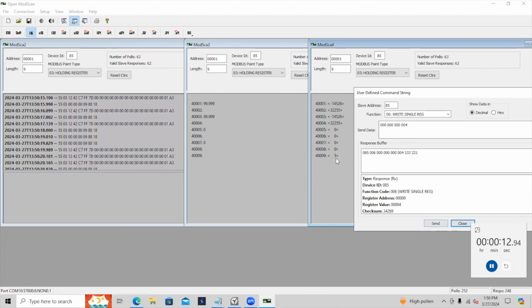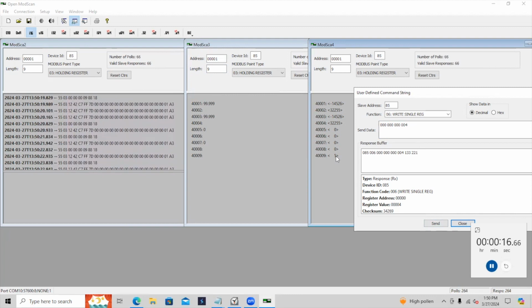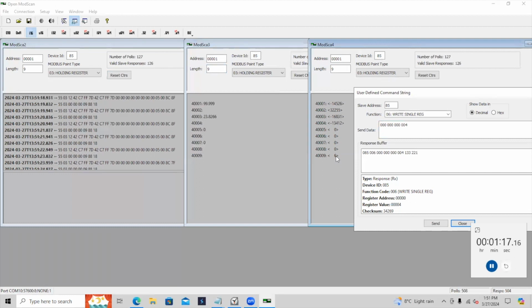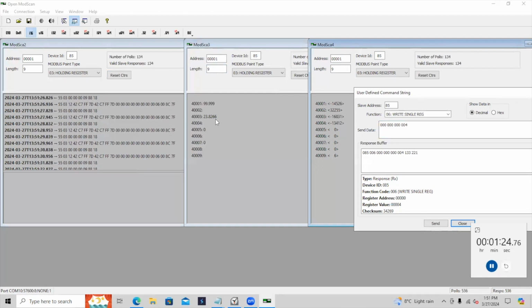You can see first the transducer health appears here as number 5, showing that it's doing its reference validation checks. While it's doing its reference validation checks, we don't measure the temperature to save some time. We can now see the transducer health has changed to 6, showing that it's now starting to do pH activation, and the temperature has changed to 23, showing that it's now recording a temperature. If we look on this screen here, you can see that we're polling every second, and the sensor is responding within 200 milliseconds.